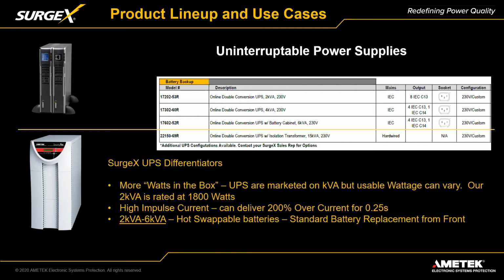UPSs are sold by their kVA number, you've seen that all the time, but you have to look in the specs to see how much wattage it can deliver. You see this a lot with the APC models, where it might say it's a 2200 VA unit, but it can only deliver 16 or 1700 watts. Our 2 kVA unit can deliver 1800 watts, which is a really efficient design.